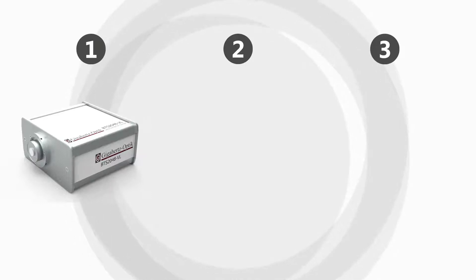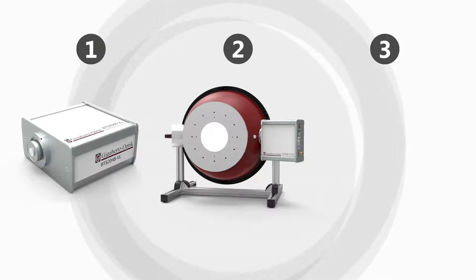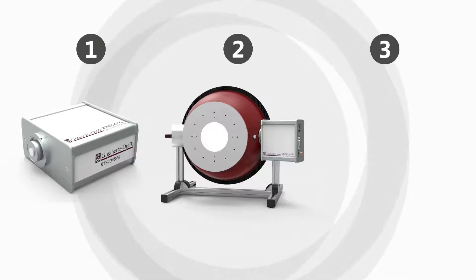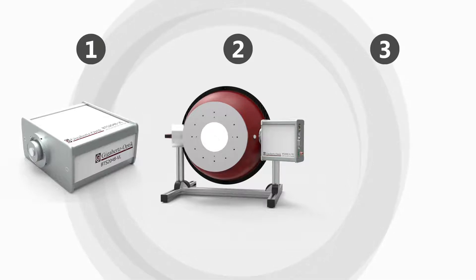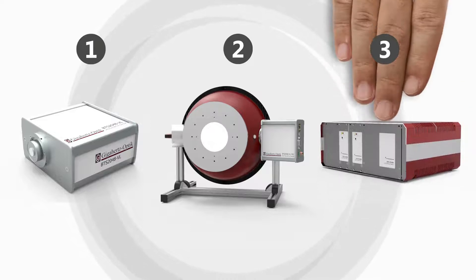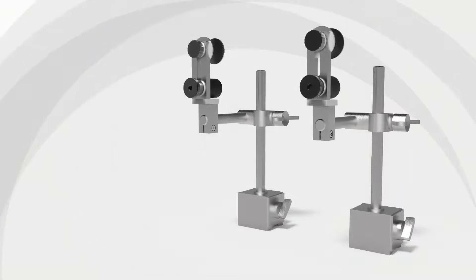Since light sources and light guides come in many different shapes, an integrating sphere is required which collects the emitted light. Exchangeable apertures allow the creation of tailored fittings for each light source and light guide shape. Light sources need power to function, therefore the TFCT25 also includes a power supply. Its triggering function allows the emission of short light pulses and their synchronized measurement via the spectral radiometer. Sample holders with magnetic bases allow the flexible positioning of light guides with complex shapes while still allowing their stable fixture. A magnetic steel tabletop is recommended for their use.